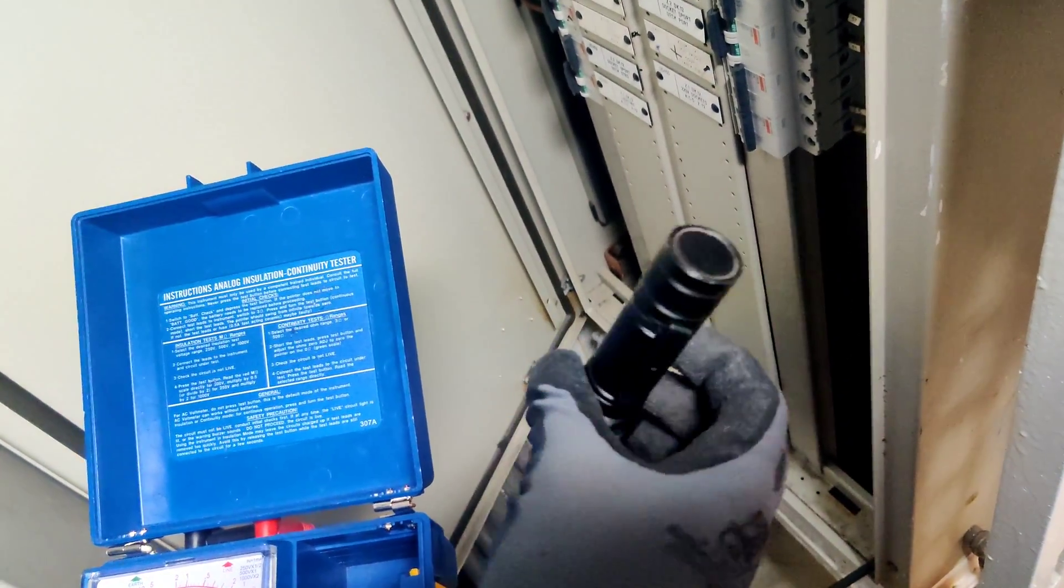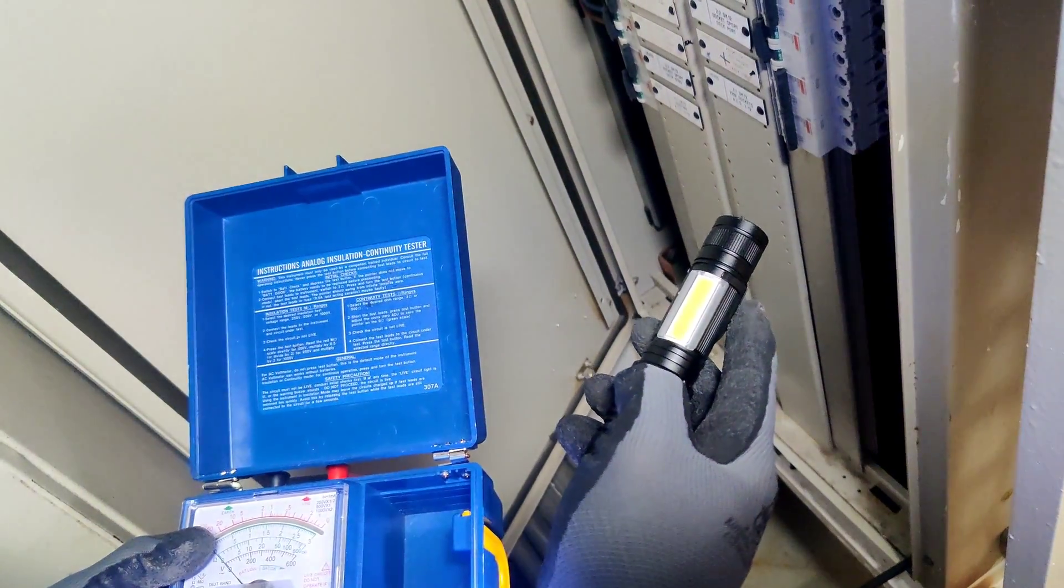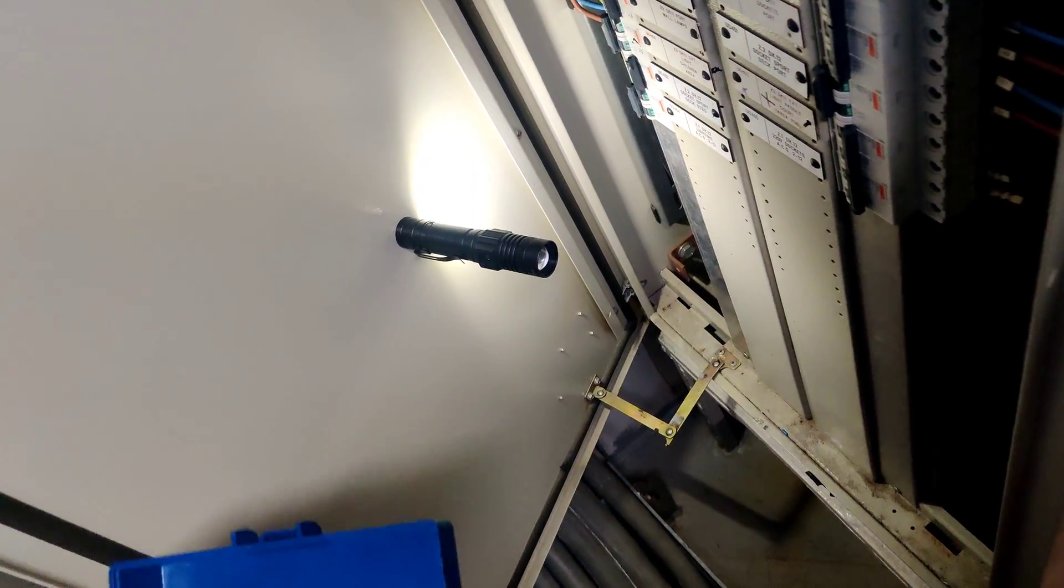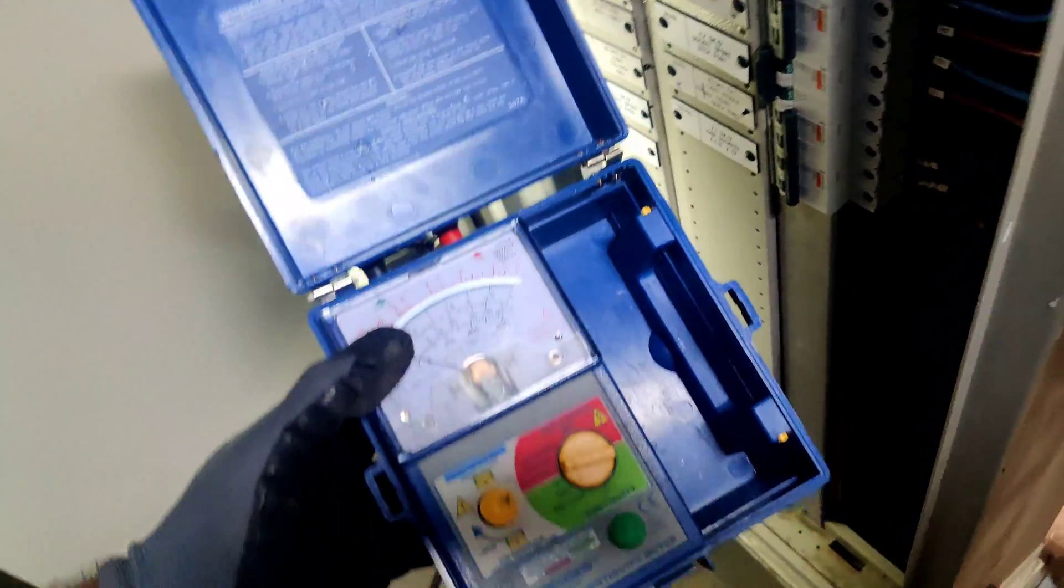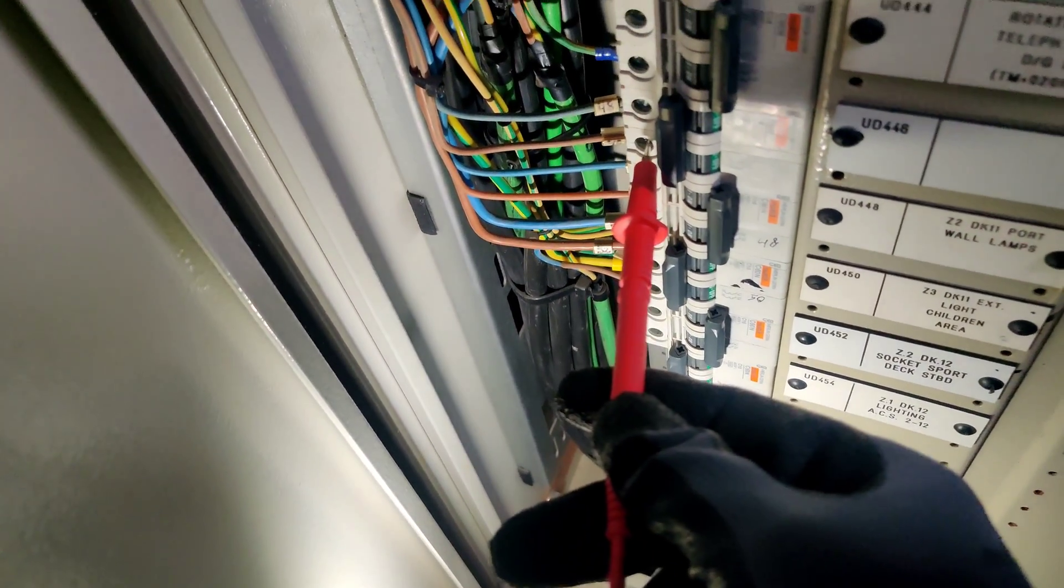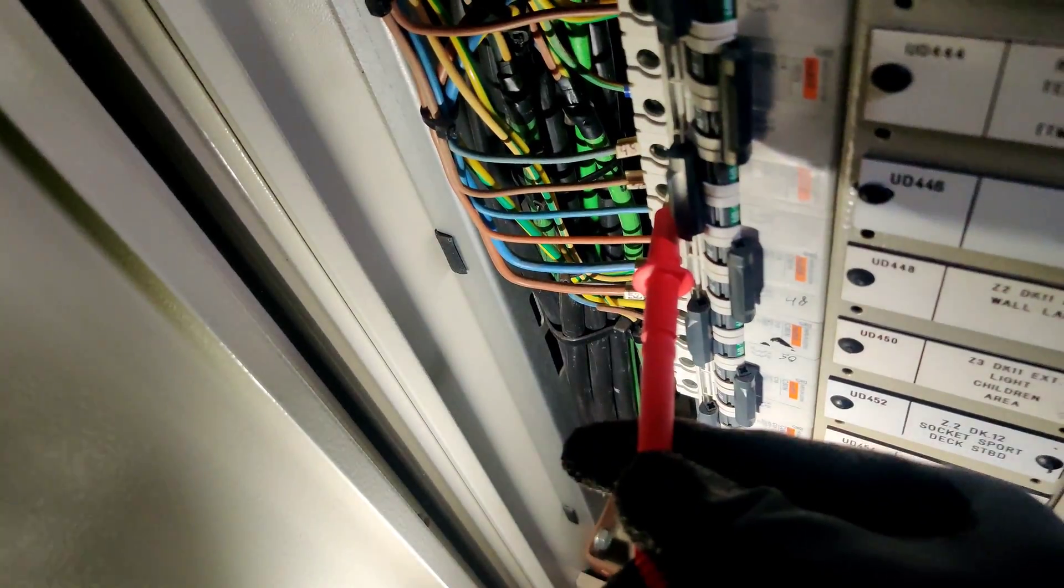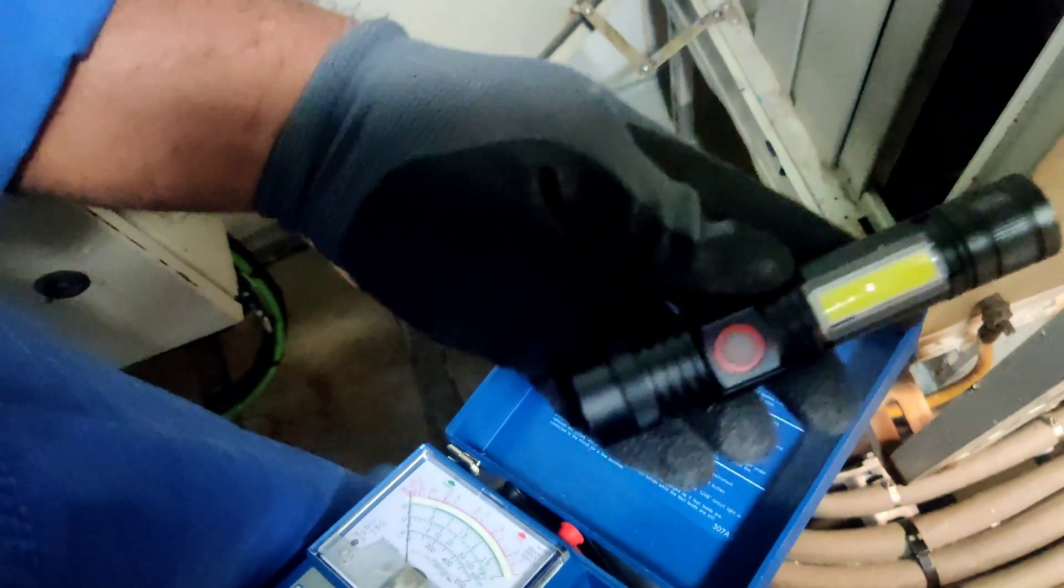So this is the flashlight that will attach to the panel. This flashlight you can buy from Amazon. It is around 17 USD. Now we are going to connect the lead wire properly. Now showing very less mega ohm. That means that light was grounded.